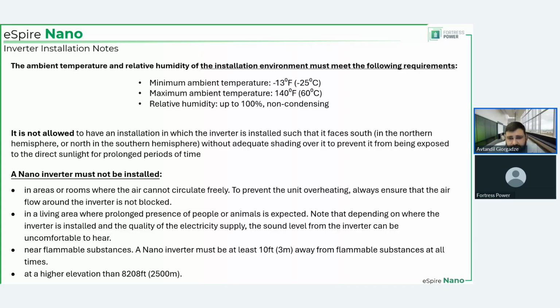If you're installing this inverter in the northern hemisphere, it should not be on a south-facing wall, unless there is an adequate amount of shading, so it's not exposed to direct sunlight for the entire day. And if you're in the southern hemisphere, it should not be installed onto a north-facing wall, right? And for obvious reasons, if it's constantly exposed to direct sunlight, that screen is going to burn. The inverter will struggle to cool itself down. So, again, please do follow these rules. They are there for a reason. If you have adequate shading, that's fine though. What we're trying to prevent is direct sun exposure.